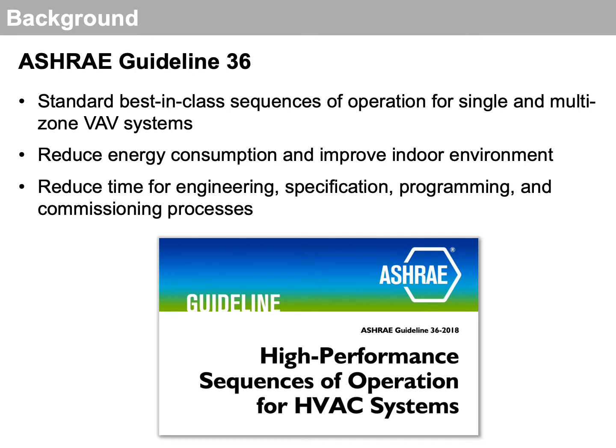And really there are two main purposes of this standard. First, it's to reduce energy consumption in a large number of buildings, as well as improve the indoor environment, both in terms of thermal environment and indoor air quality. And the second is, by publishing these standard sequences, to help reduce the time for engineering, specification, programming, and commissioning processes that the industry sees in developing and implementing sequences.